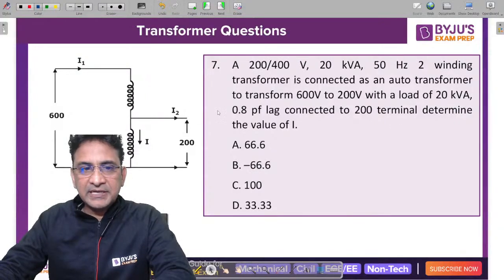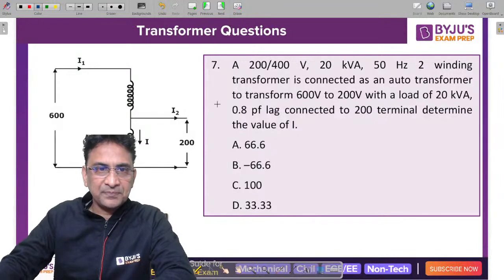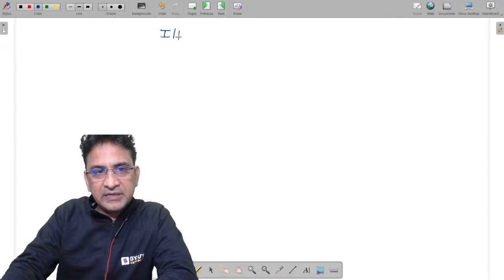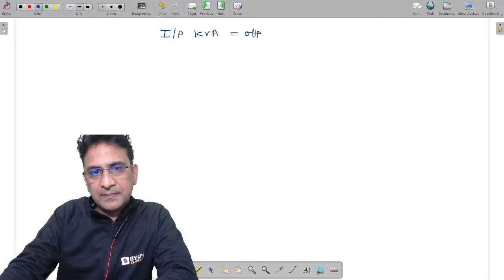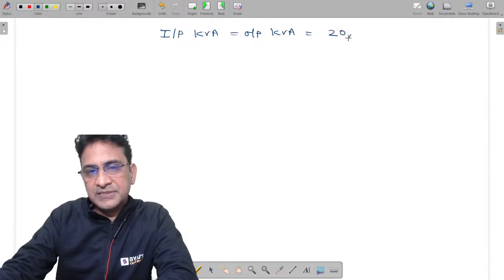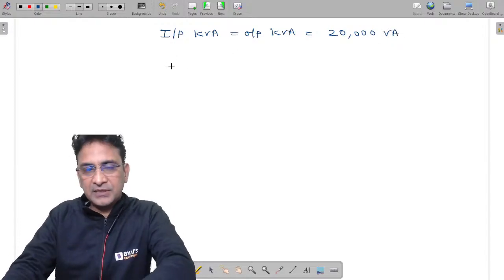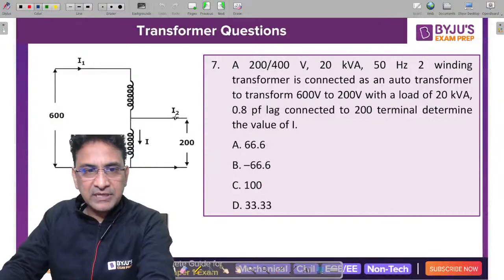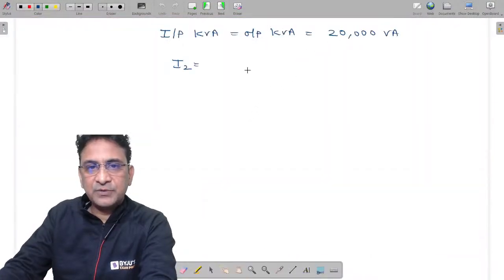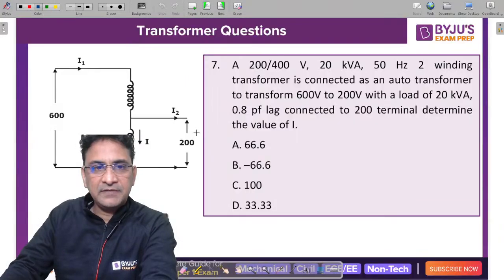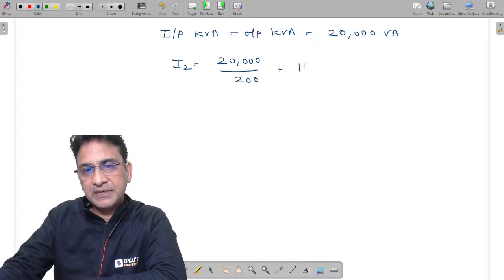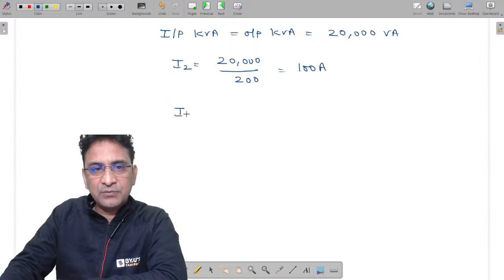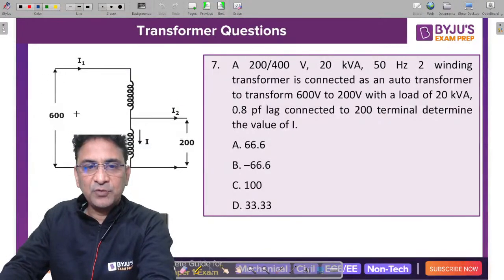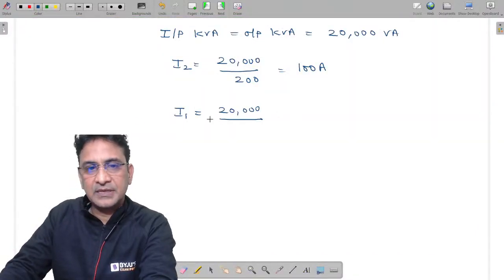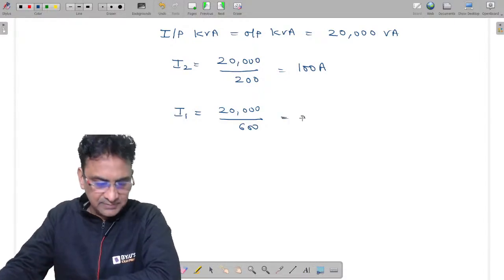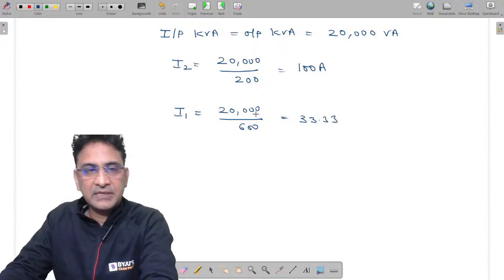See, 20 kVA is the connected load. That means the transformer is supplying 20 kVA output power. In a transformer, input power is equivalent to output power, meaning input kVA is equivalent to output kVA. So the transformer is supplying 20,000 volt ampere. If I find the current flowing through the load, I2, voltage is 200 volt and VA is 20 kVA. So it is 20,000 divided by 200, which becomes 100 ampere. Now the current drawn from the supply, I1: input volt ampere is also 20 kVA, so 20,000 divided by 600 volt. It will come 33.33. So we have calculated the values of I1 and I2.